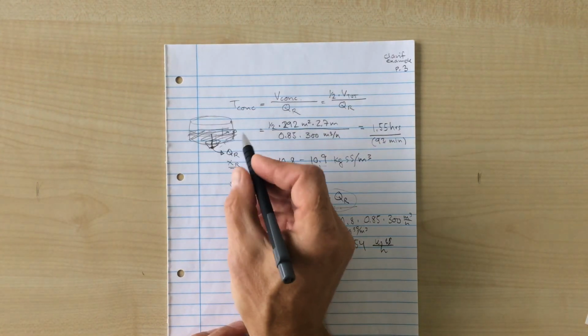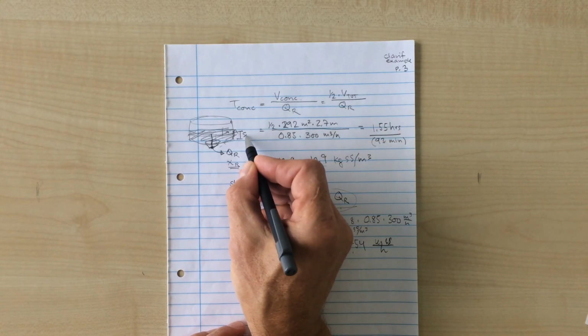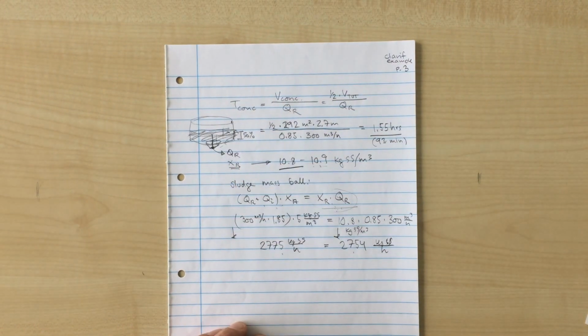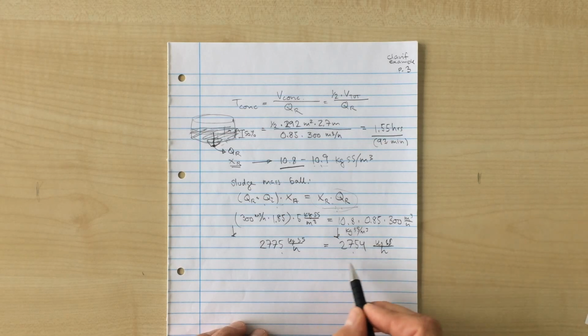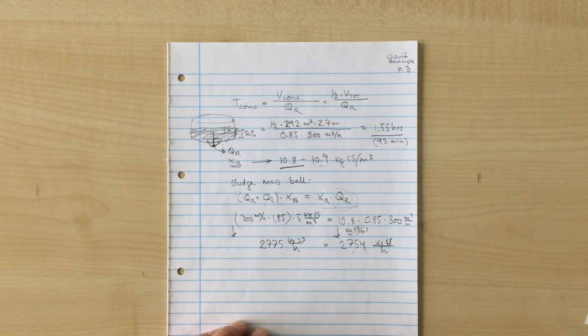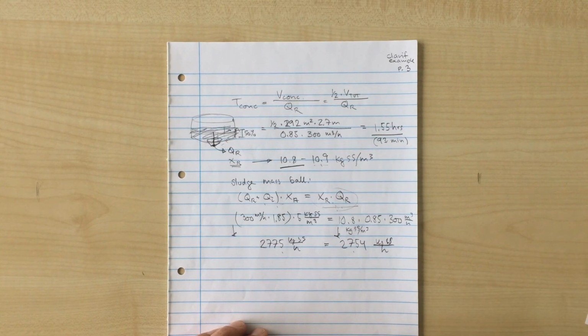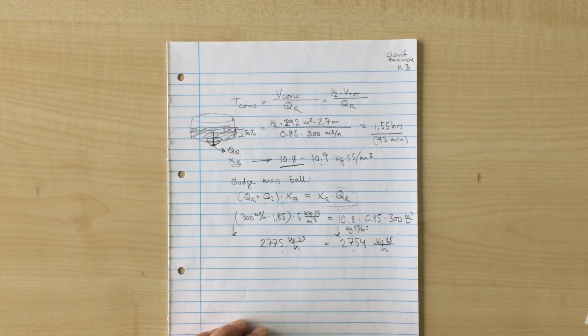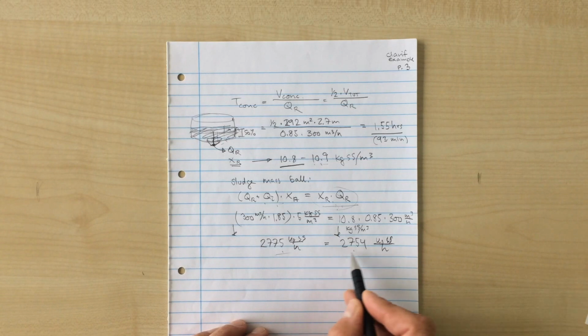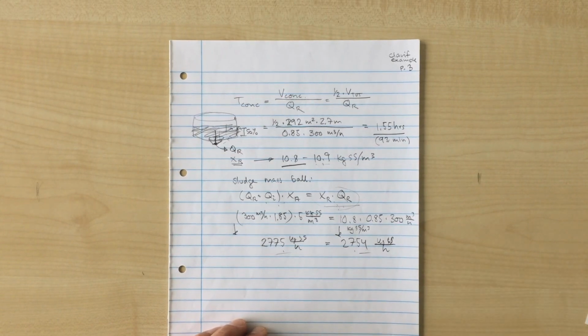But it's not allowed for me to go up to more than 50% of the maximum volume according to the design set here. So the conclusion is that I need a deeper clarifier, or a larger clarifier, a bigger area. But I can also see that I'm pretty close, so I'm roughly where I am supposed to be.